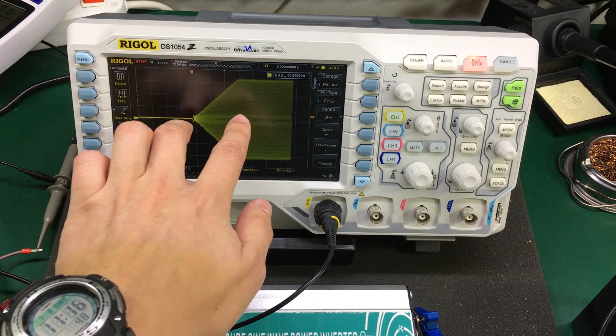I'm also interested in the startup behavior, so I've set the scope for single capture, and now I'm going to turn on the inverter. We can see the voltage is slowly rising up to the 227 RMS, but I don't see any overshoots or anything funny going on. It just takes approximately 3 seconds for the voltage to reach the maximum voltage.